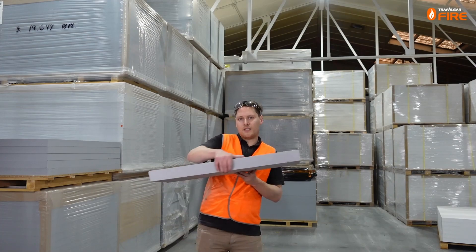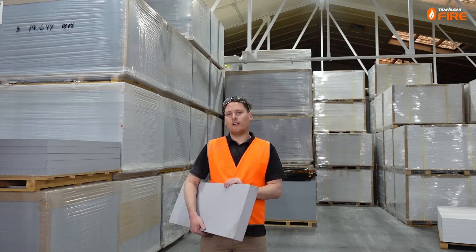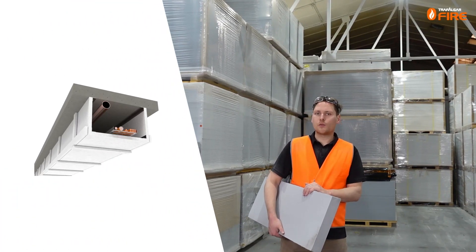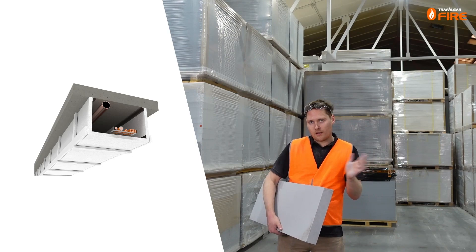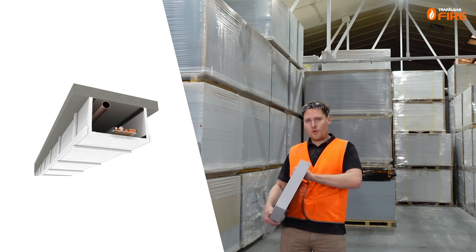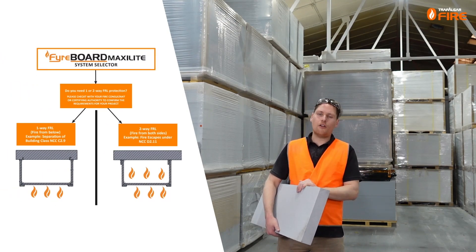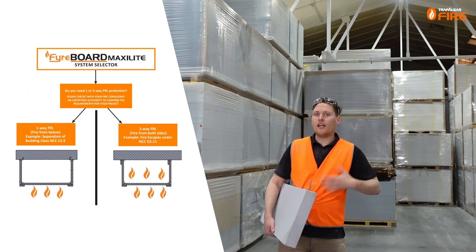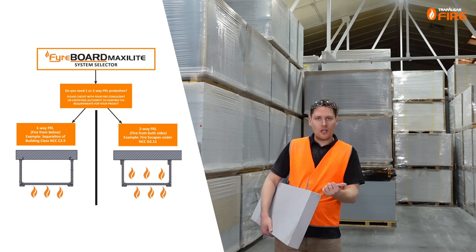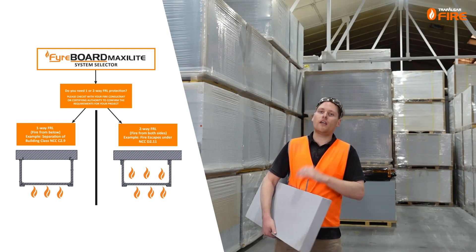Today we'll be looking at our 60 millimeter thick MaxiLite board to create a two-hour two-way FRL bulkhead ceiling system for applications like fire escapes, where there is a risk of fire from inside and outside of the bulkhead — for that application you do need the 60 millimeter thick board. If you're constructing a bulkhead or ceiling that only has fire from one side, you can use the 30mm or 40mm boards as well as the 60mm for a one-way FRL system.